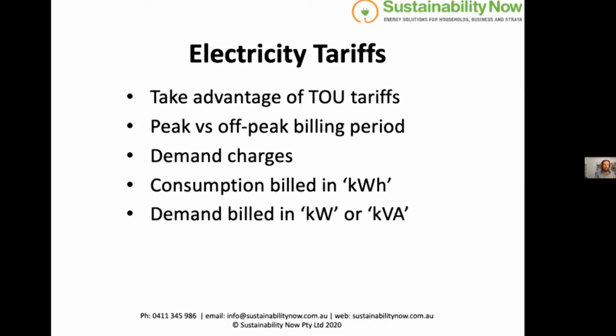One building in particular, I noticed a contractor was doing routine testing on car park ventilation fans right in the middle of peak billing periods. And the result was that the building's billed kVA demand charge doubled just because of testing. It was costing them something like $14,000 a year extra, or more than it needed to, just because the contractor didn't understand how the tariff worked.